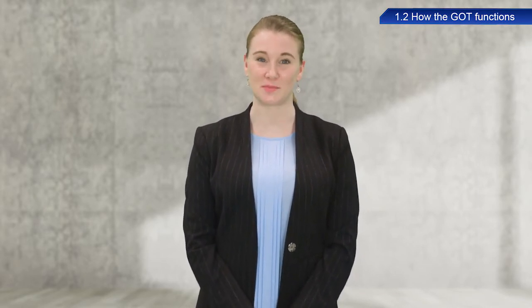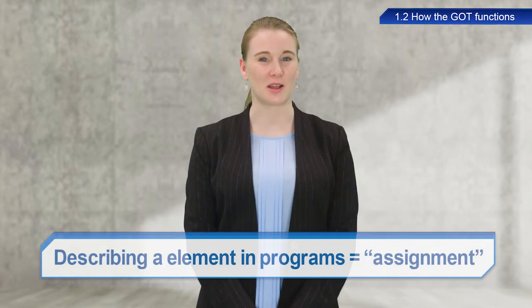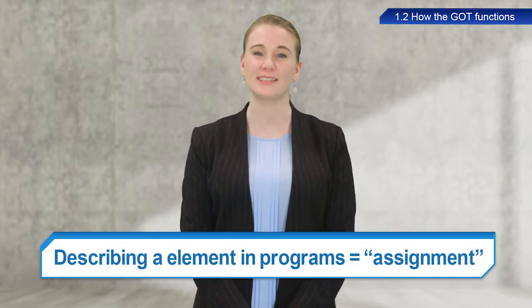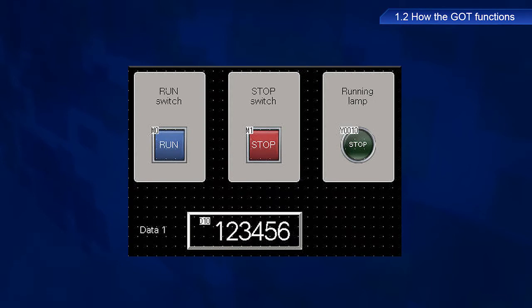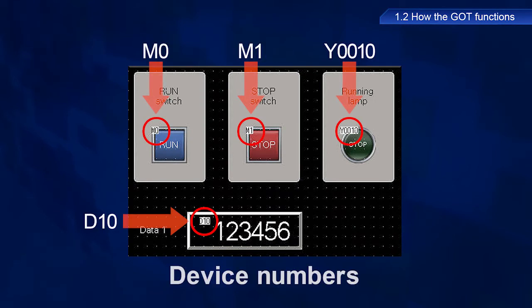Do you now have a better understanding of the relationship between GOTs and PLC programs? GOT switches and lamps must be described in PLC programs to have functionality. Describing these elements in programs is referred to as assignment. The text string M0 has been assigned to the GOT run switch. These assigned text strings such as M0 and D10 are referred to as device numbers. Device numbers are assigned to other switches and lamps in the same way. Please remember these terms as they will continue to be used throughout this training.